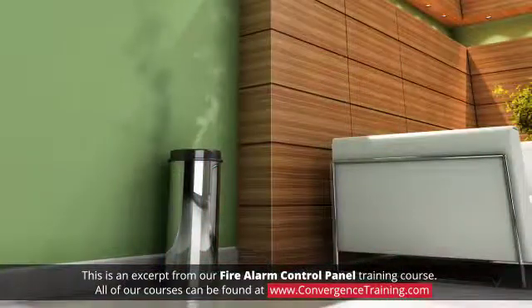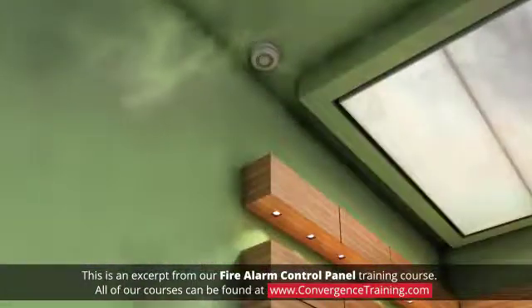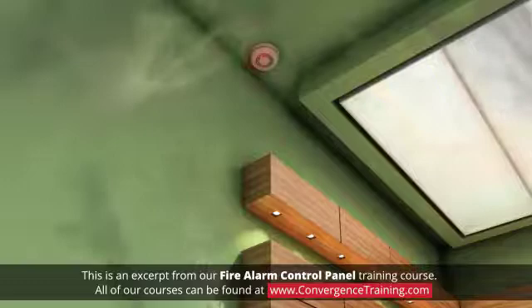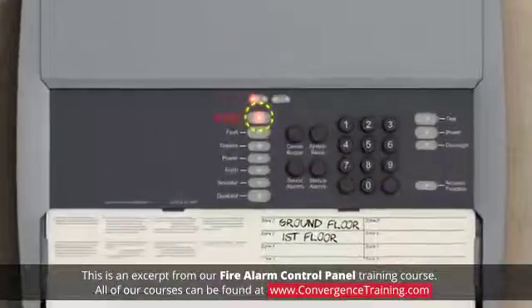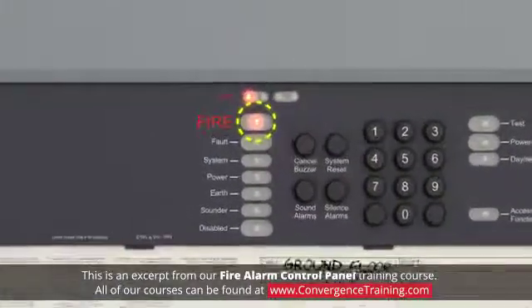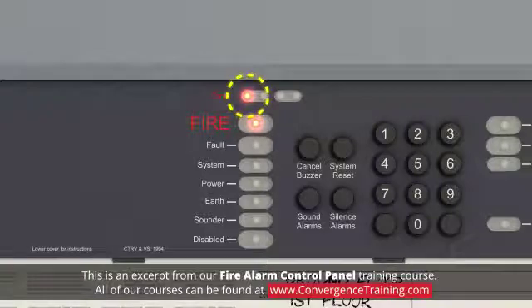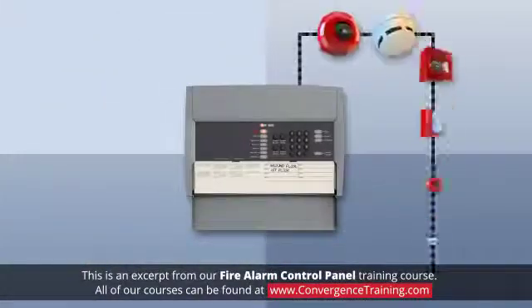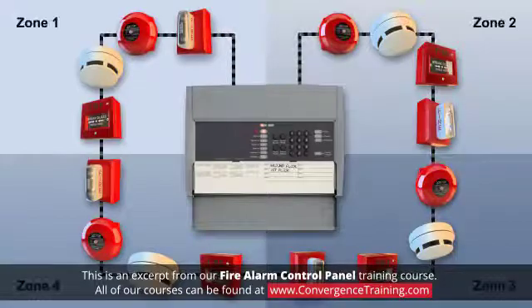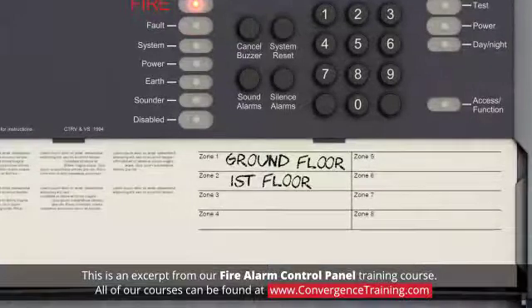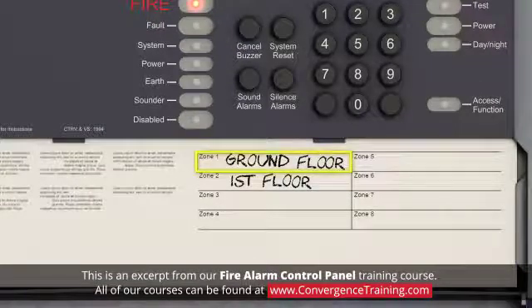In this type of fire system, let's say a smoke detector is activated on the ground floor of the building. You would observe a red LED indicating a fire activation is illuminated on the fire control panel. You would also see another red LED in zone 1. The panel in this type of system is configured to show zones of the locations of the fire detection devices. If you looked at the zone listing, you would see that zone 1 is located on the ground floor.